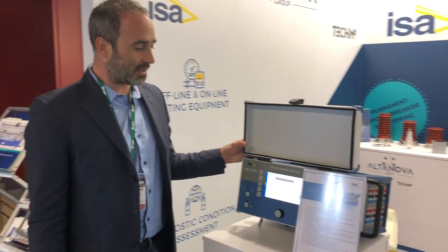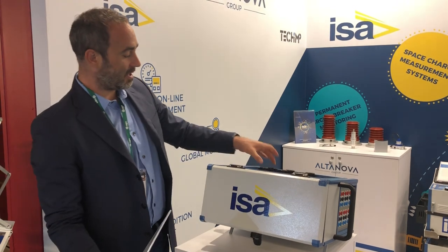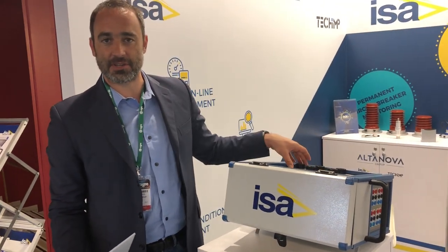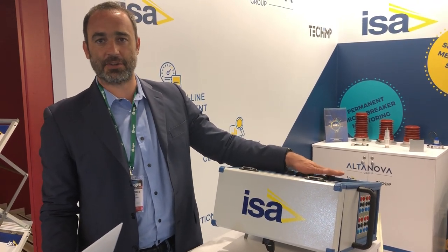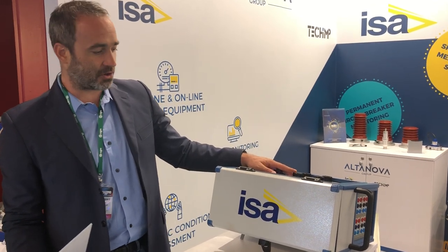From ISA we have the CBA 3000, which is a circuit breaker analyzer with a special ability to do three-phase micro-ohmmeter measurements. In that case, with one connection, if your circuit breaker is grounded on both sides, you can measure the time and the resistance of your circuit breaker's main contacts.